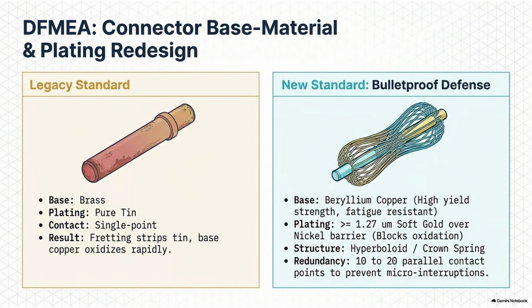Right. The spec says they upgrade the base metal of the terminal to beryllium copper. Beryllium copper. That sounds expensive. It's a legendary alloy in aerospace and military applications. By adding a small amount of beryllium to the copper matrix, you fundamentally change its crystal lattice structure. So it gets stronger. It gains an incredibly high yield strength and severe fatigue resistance. It acts like a very stiff, nearly indestructible spring that won't snap under vibration.